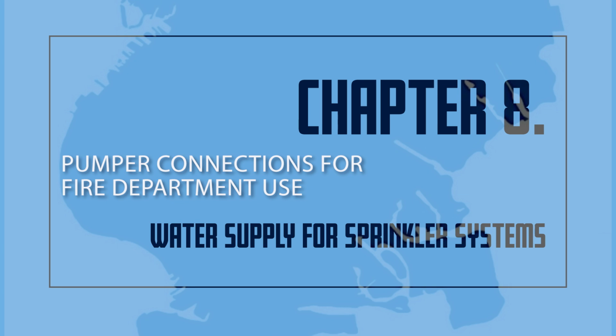When responding to an alarm, most fire departments supply water to the standpipe system first. The standpipe system supplies water to the fire hoses to be used within the building. Water is then supplied to the sprinkler system through its own fire department connection. Care should be taken that the standpipe and the sprinkler connections are properly marked because the connections look the same. The exact purpose of each fire department connection should be shown nearby or on the fire department connection itself.